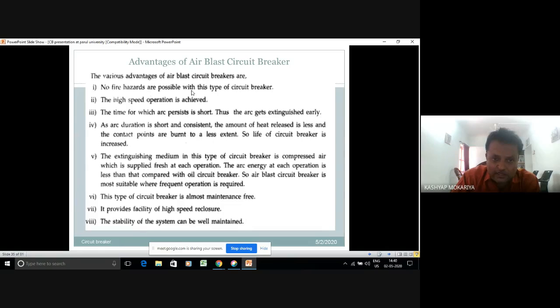Advantages: no fire hazards are possible with this type of breaker. High speed operation is achieved. The time for which the arc persists is short, thus the arc gets extinguished early. As the arc duration is short and consistent, the amount of heat released is less, and the contact points are burnt to a lesser extent. So the life of the circuit breaker is increased. The extinguishing medium in this type of circuit breaker is compressed air, which is supplied fresh at each operation. The arc energy at each operation is less compared with an oil circuit breaker.